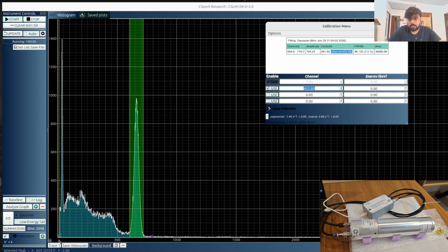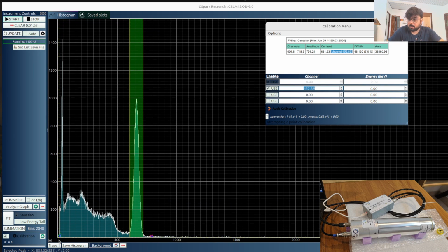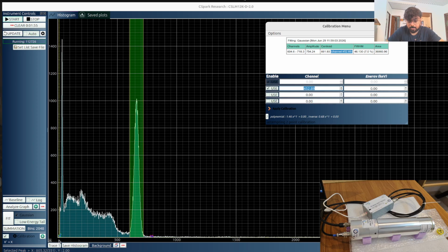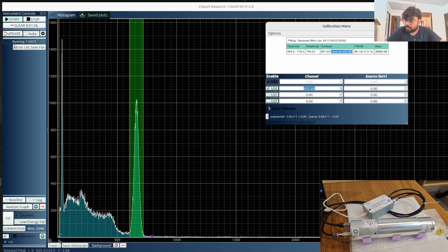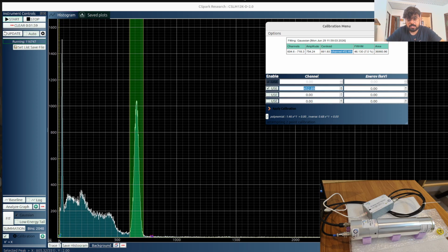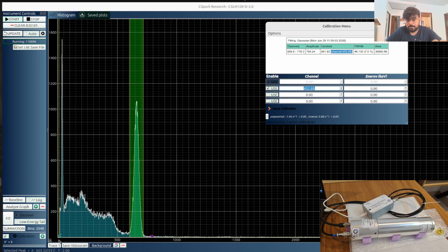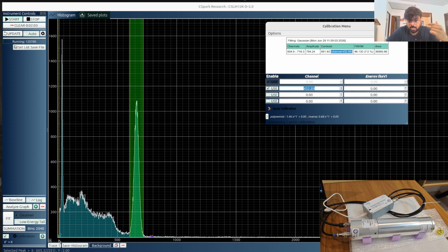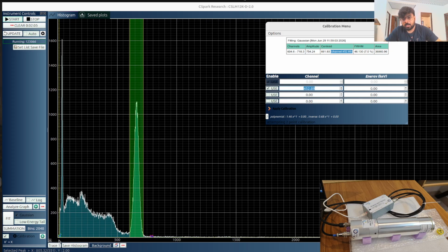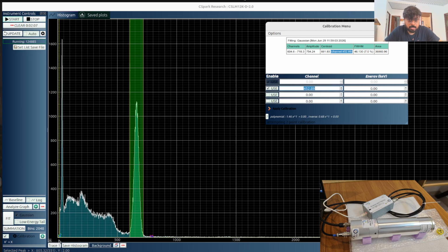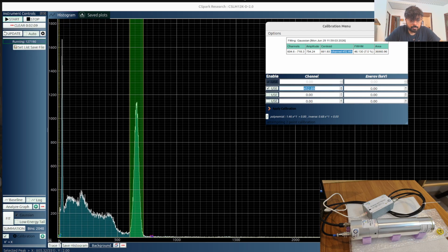The normal process for instruments is that you calibrate it every time you use it, because there are temperature coefficients that will come into play. For example, your sodium iodide scintillator has an efficiency that changes by about 0.3% for every degree in temperature change. So this is going to affect your readings, right? So you calibrate it at whatever temperature you're using it in.